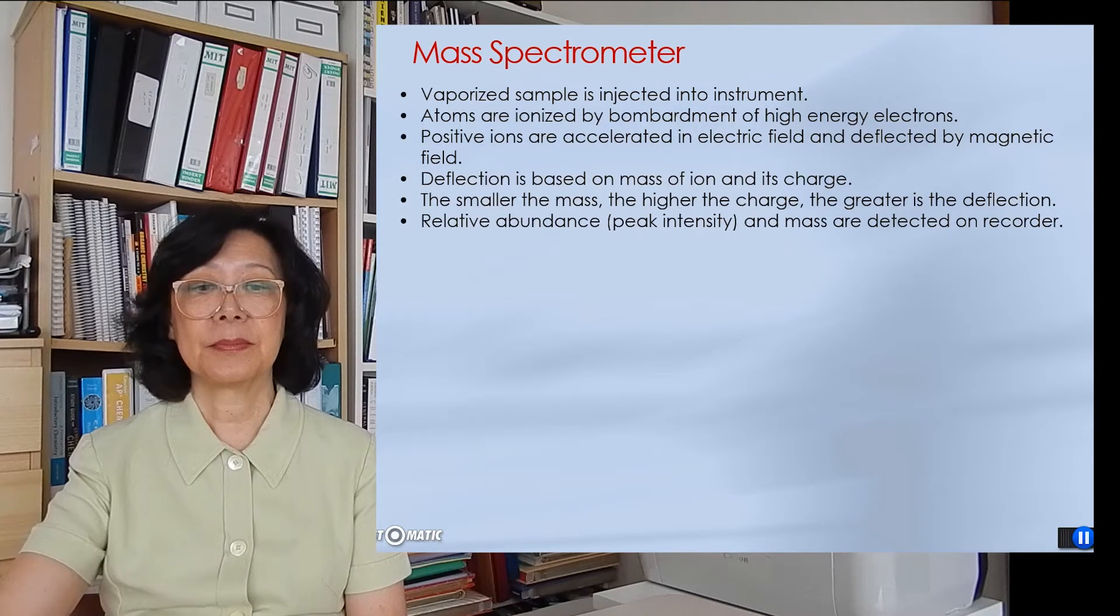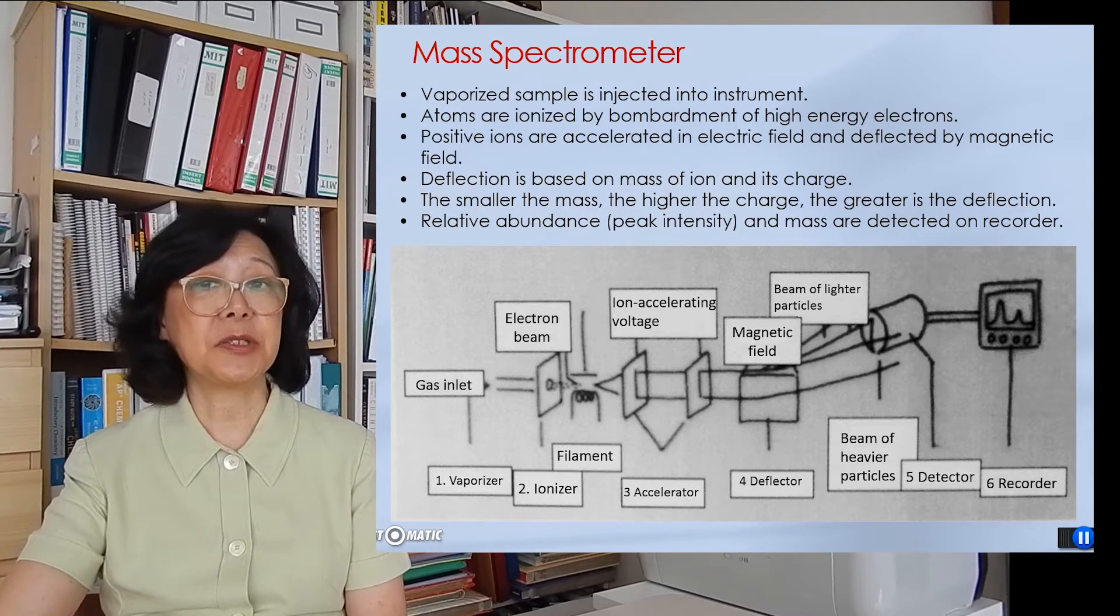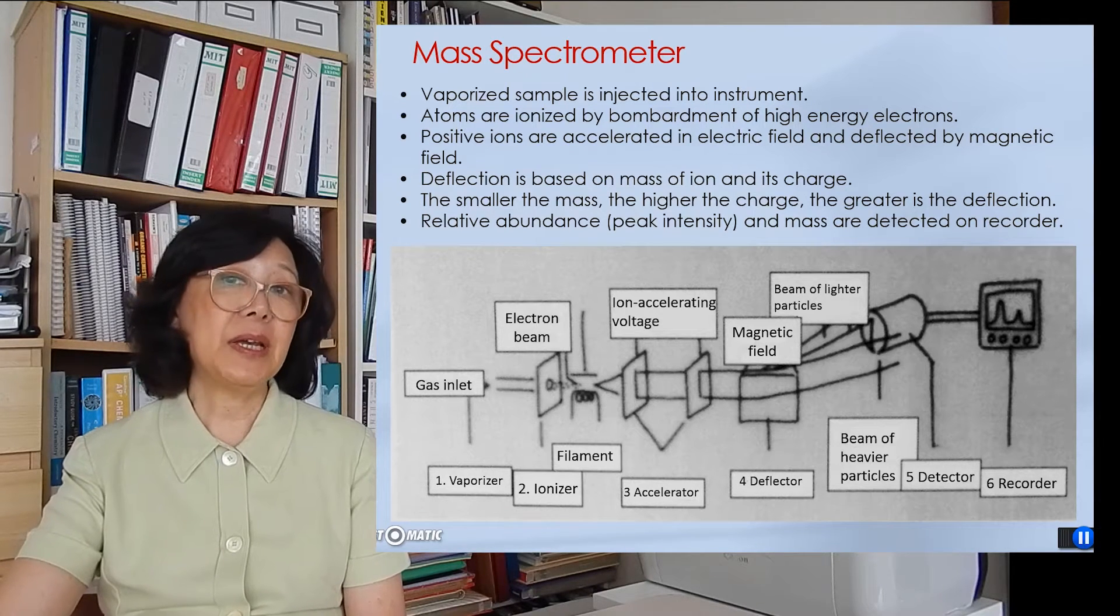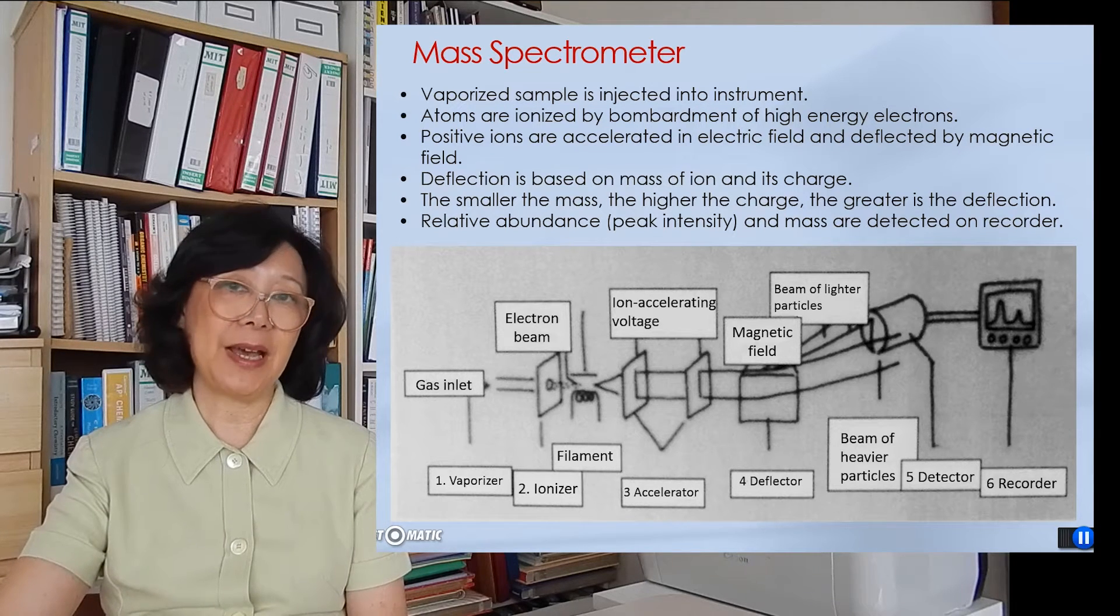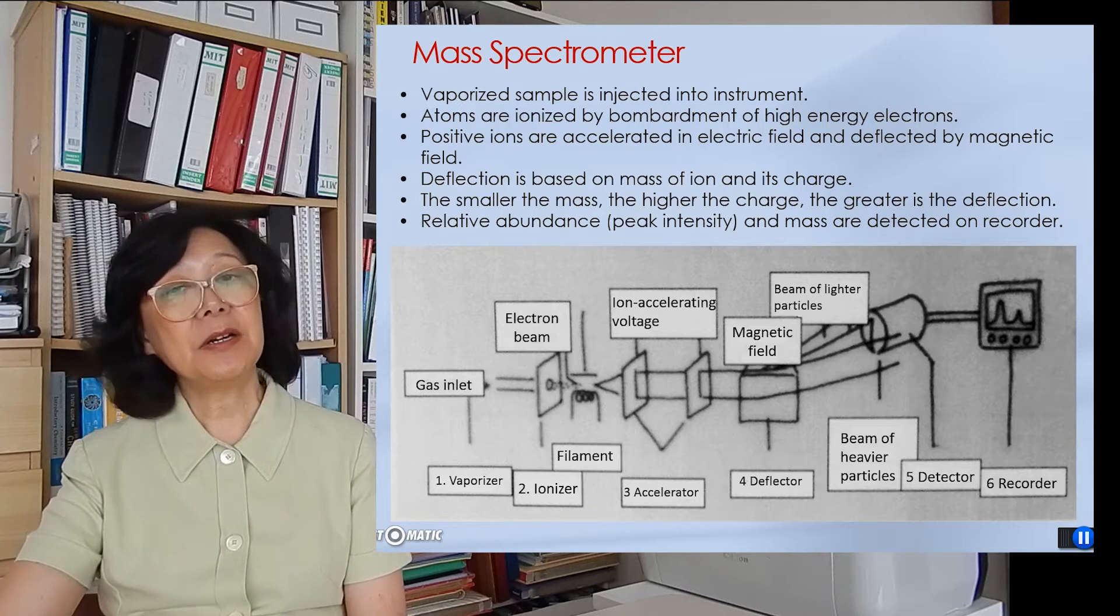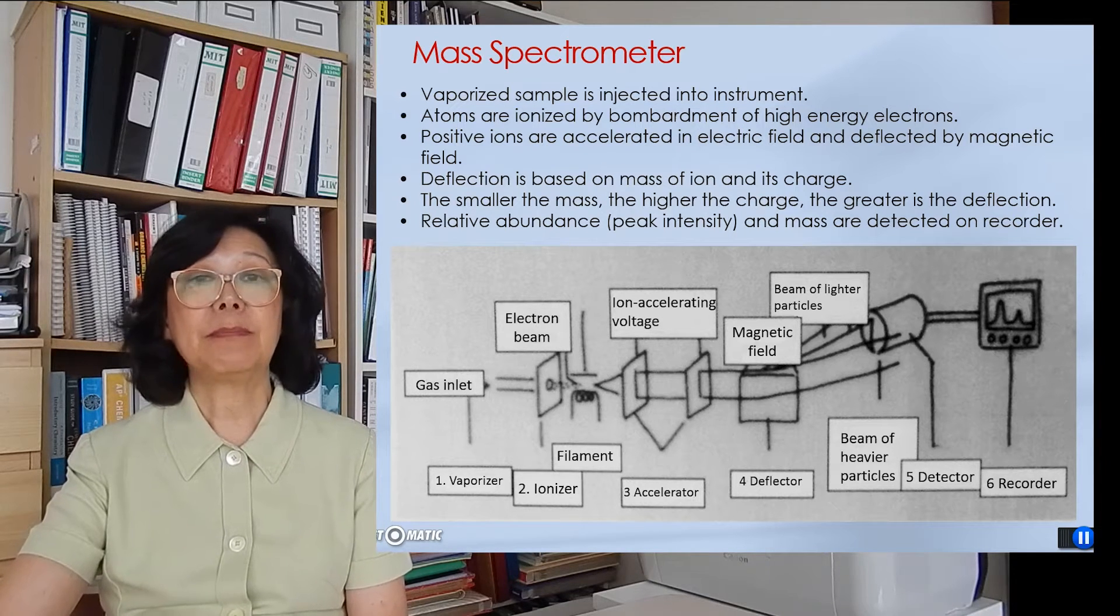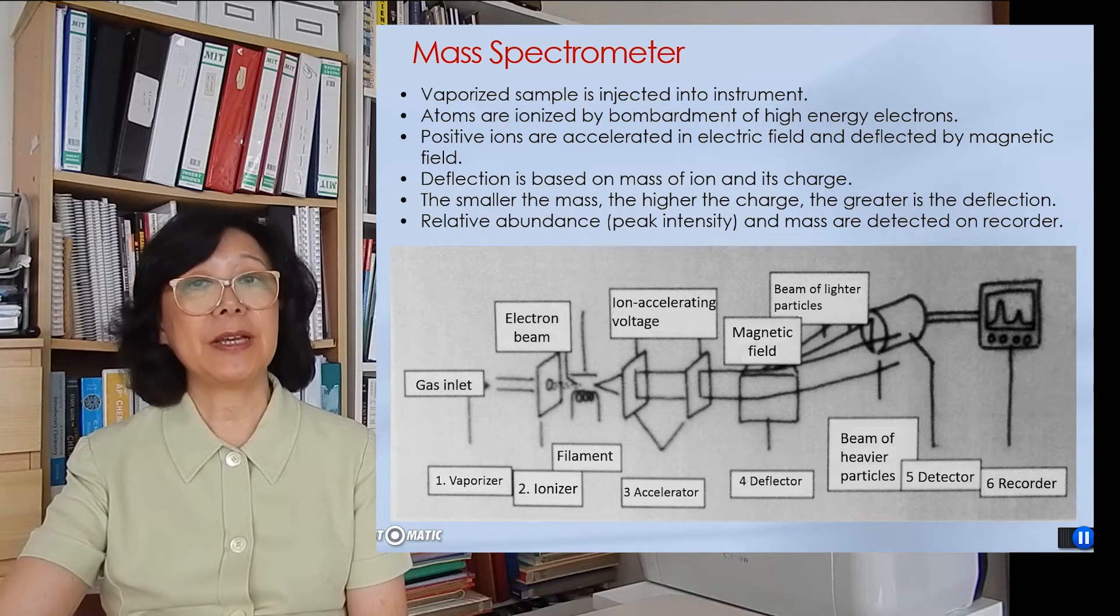So how does a mass spectrometer work? Here is a diagram that shows first the sample is vaporized into gas form and injected into the instrument. Then being bombarded with high energy electron beams that knock off the valence electrons from the atoms to turn them into positive ions. These ions are then accelerated through the electrical field and bent by the magnetic field. Now the bending depends on the mass and the charge of the ions.